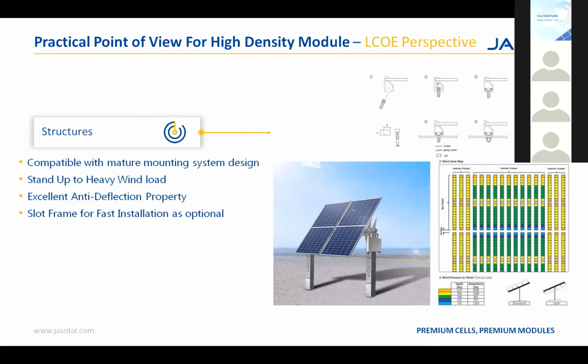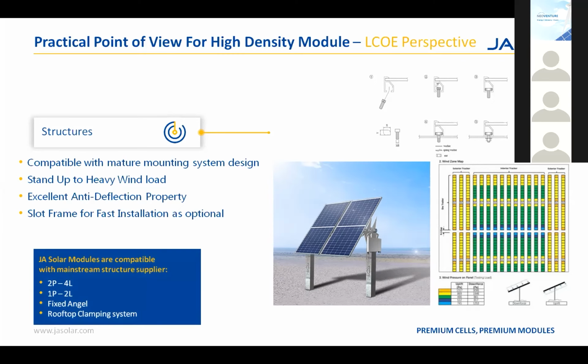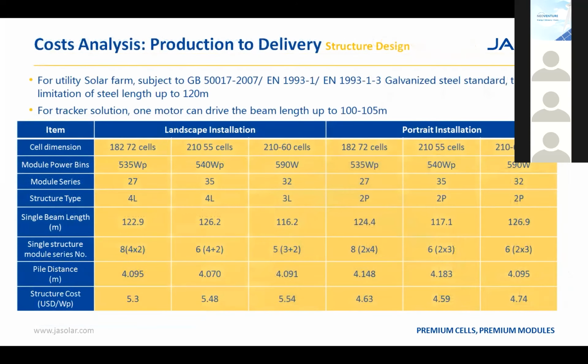And besides, for the design, there is a slot frame for faster module installation as an option. And for tracker system, the modules are compatible with either 2 portrait or landscape installation, or 1 portrait or landscape installation. Of course, we are compatible with fixed angle mounting system installation and the rooftop clamping system. And from the structure design point of view, compared with M12 55 cells and M12 60 cells, for portrait and landscape installation, the cost with 182 millimeter module will be lower than others too. This is an analysis based on the standard EN 1993-1 galvanized steel standard. And besides, due to the tracker motor limit, the maximum beam length is defined up to 100 to 105 meters.